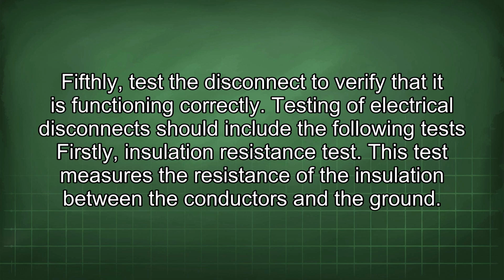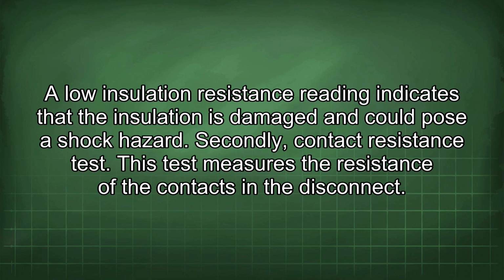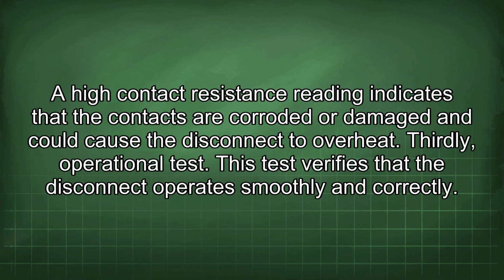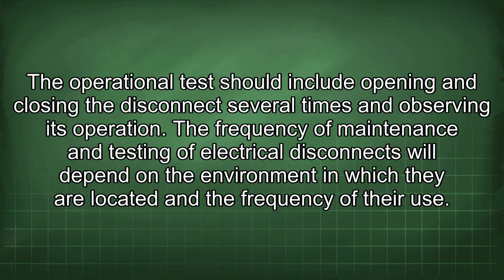Testing of an electrical disconnect should include the following tests. Firstly, insulation resistance test. This test measures the resistance of the insulation between the conductors and the ground. A low insulation resistance reading indicates that the insulation is damaged and could pose a shock hazard. Secondly, contact resistance test. This test measures the resistance of the contacts in the disconnect. A high contact resistance reading indicates that the contacts are corroded or damaged and could cause the disconnect to overheat. Thirdly, operational test. This test verifies that the disconnect operates smoothly and correctly. The operational test should include opening and closing the disconnect several times and observing its operation.